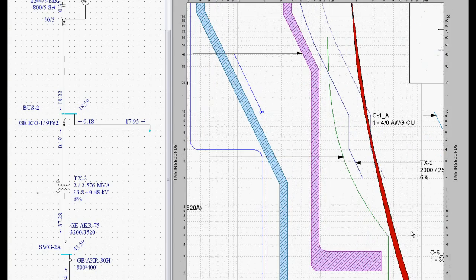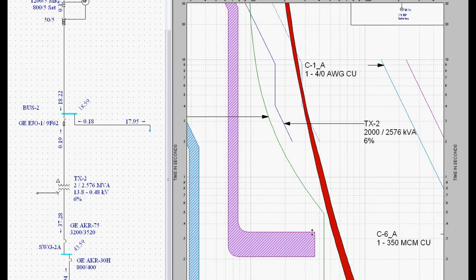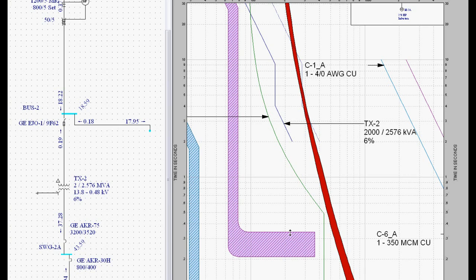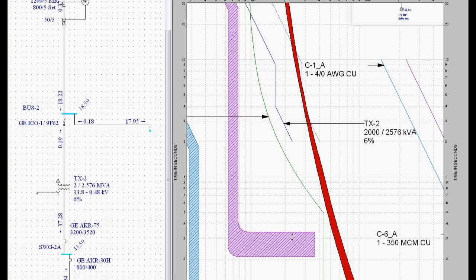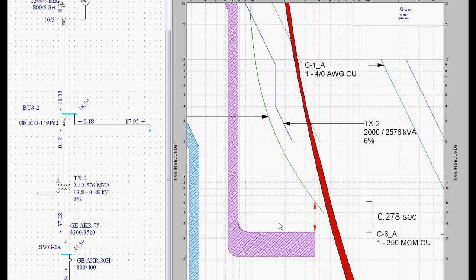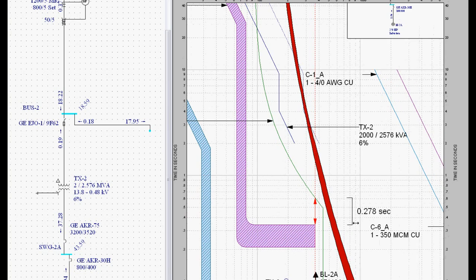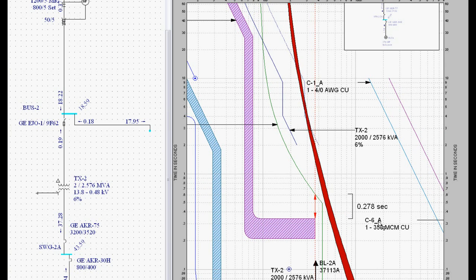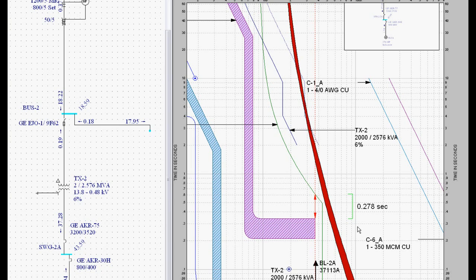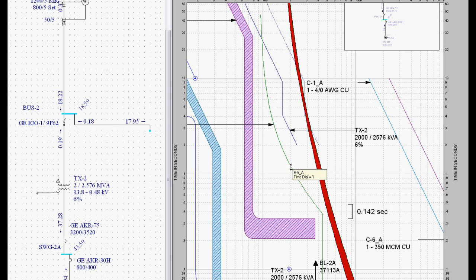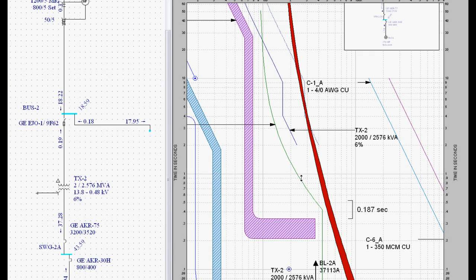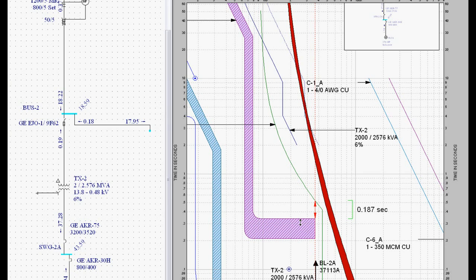The key points that you want to look at are how do you determine the time differences between different devices? Well, in EasyPower and in all Windows programs, if you want to highlight multiple devices, you hold the control key and left mouse click. And so I just highlighted these two devices. I can right mouse click, insert a difference calculator, and you can see the time separation. Now, if I drag this, notice how if I set it at time dial 1, I have 0.142 seconds of safety margin. If I set it at 1.1, I have 0.187 and so on. So I can determine based on the type of device exactly how to set this.